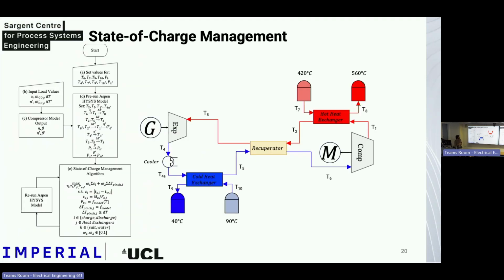I'll start with in-cycle state of charge management. This was implemented in Aspen, in the software. The goal is to ensure that neither the hot side nor the cold side runs out before the other. So when we're charging the hot side from 75% to 80%, the same happens on the cold side as well. If we let the system be, this won't happen naturally — it will just charge at different rates.